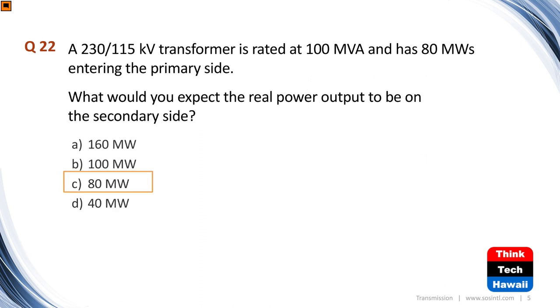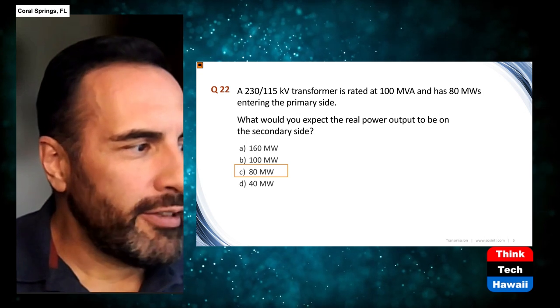So a 230 to 115 kV transformer is rated at 100 MVA, and has 80 megawatts entering the primary side. Again, another tricky question here. So what would you expect the real power output to be on the secondary side?